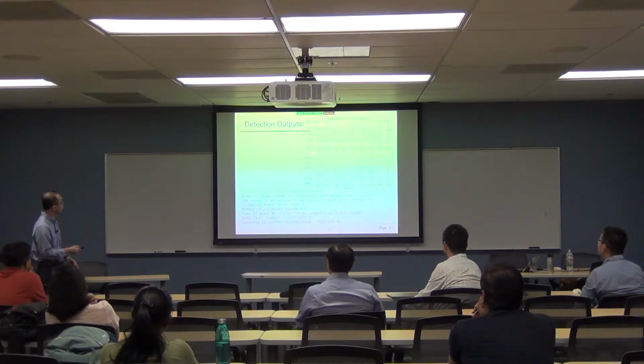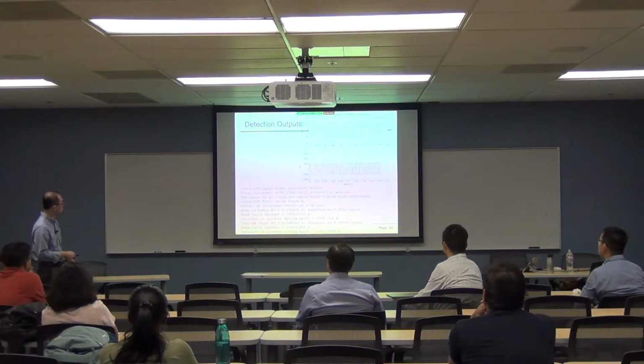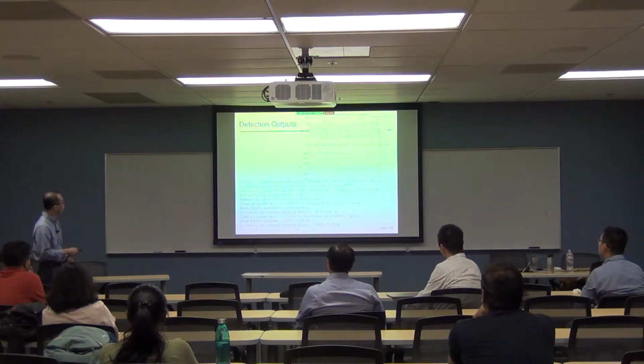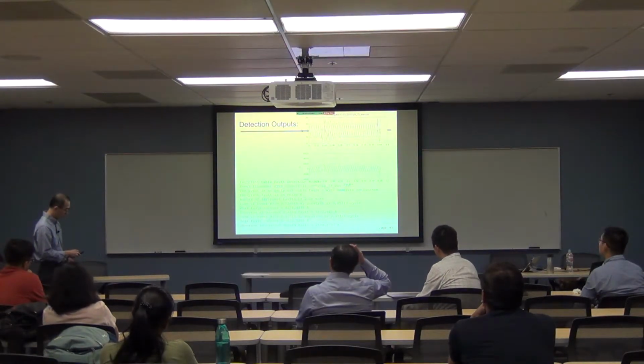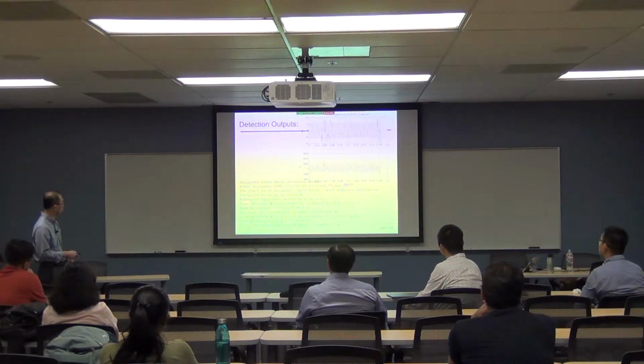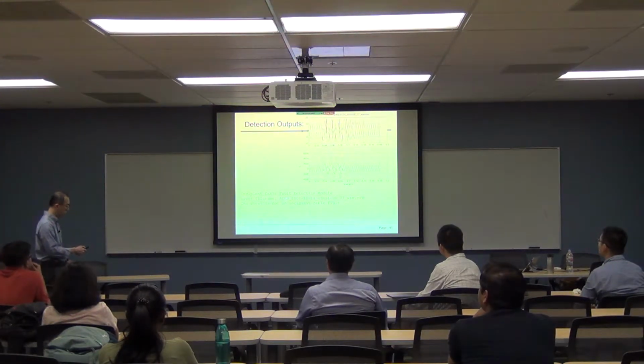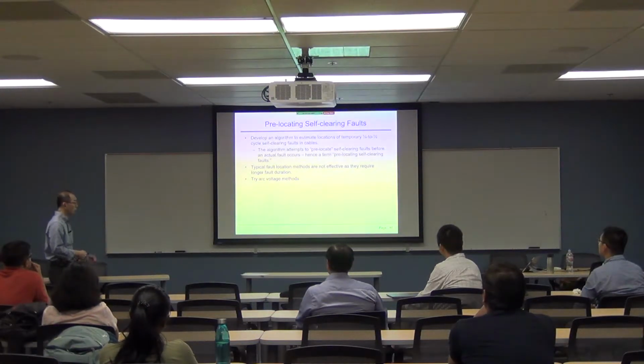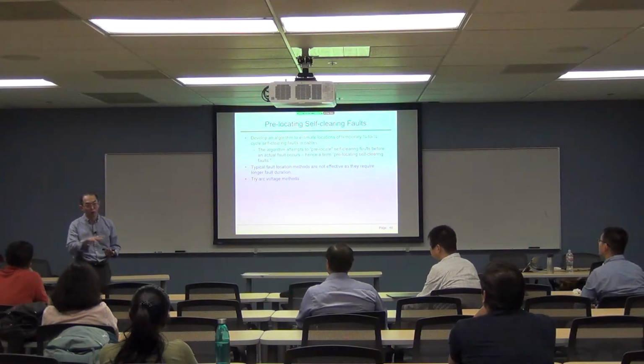Now you can see that this tells you the number of incipient faults: only 1 in here, okay? And then another one here, there are 2 incipient faults. There are 2 here, 2 or more, okay? And then in here, there are 2 also, and 2 in here. So there are 2 incipient faults. Detect all of this, and so on, okay? And then it can also tell you that this is not an incipient cable fault because this is an actual full-blown fault. So the previous part that I showed you is not very difficult to develop, okay?